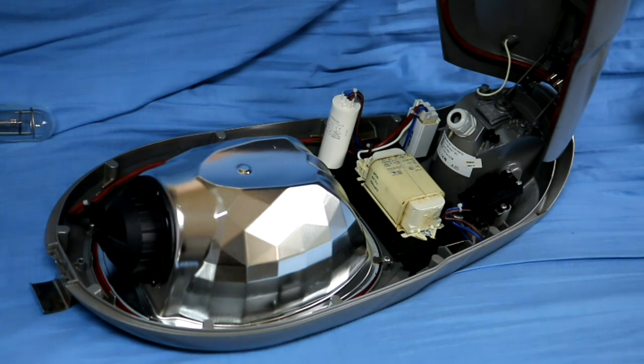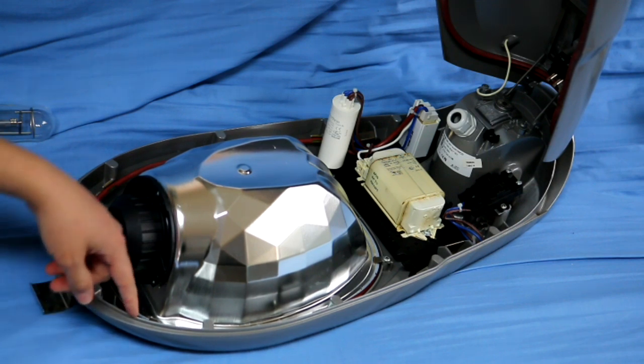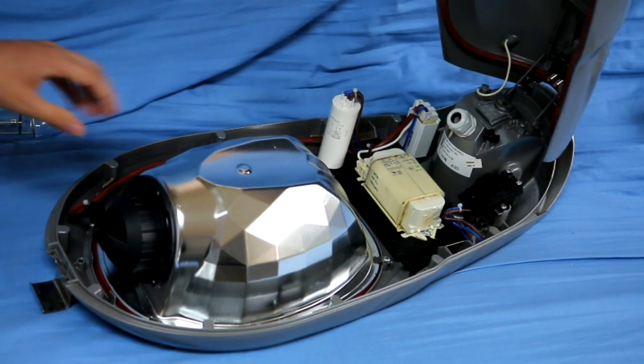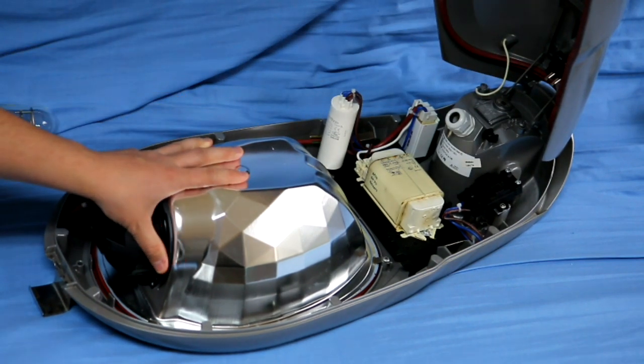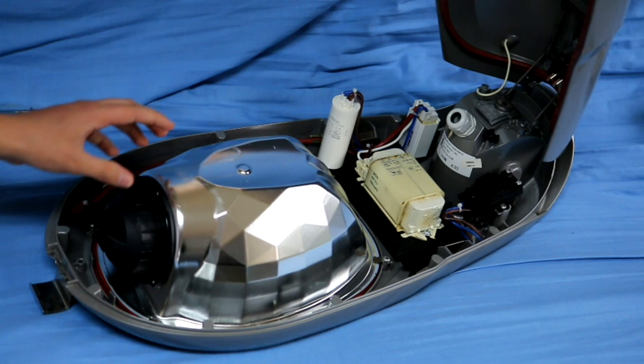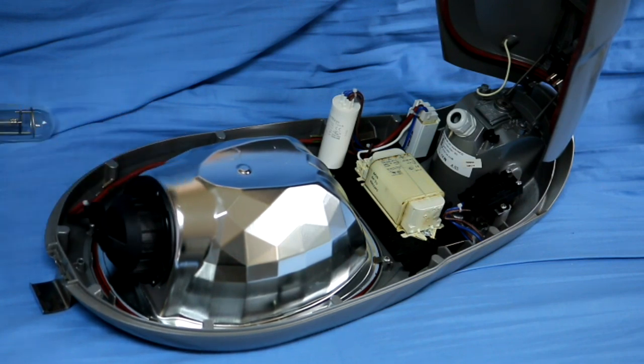Now note this is a double ingress protection model, which basically means the actual lamp unit itself by these seals there's IP66. Also the lamp compartment and the optics is also sealed to IP66. That basically means that no rubbish or moisture can get inside here and ruin the optics or the optical performance.